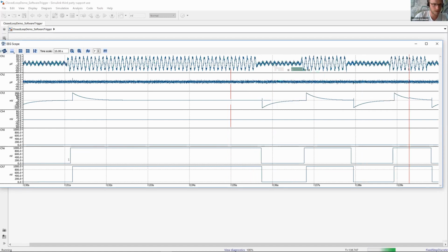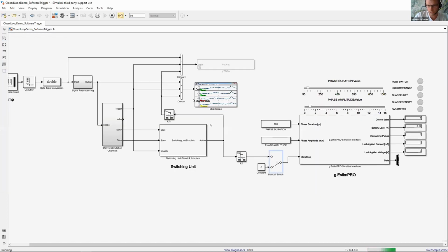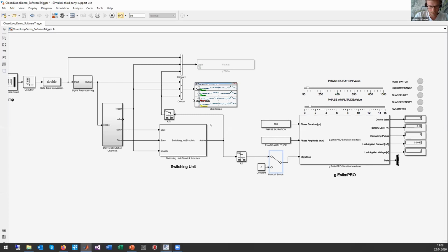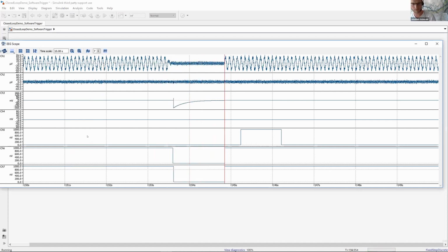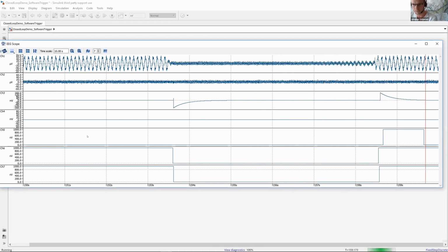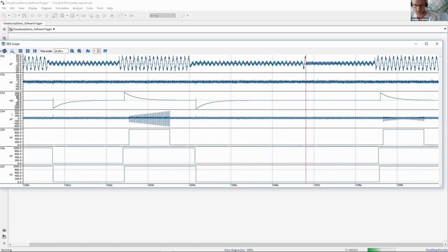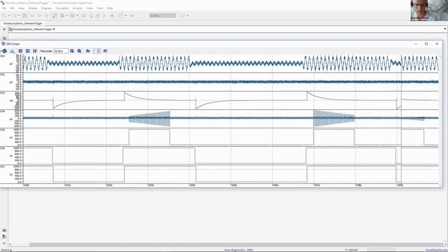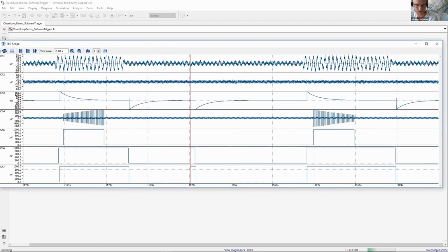Now let's take the stimulator also into account. So while the model is running, I connect the stimulator now. And let's go back to the scope. So here, yep. So in channel 5, you can now see an additional trigger signal. So this is the response from the stimulator. And you can also see here the stimulation artifacts on the channel which is still connected.